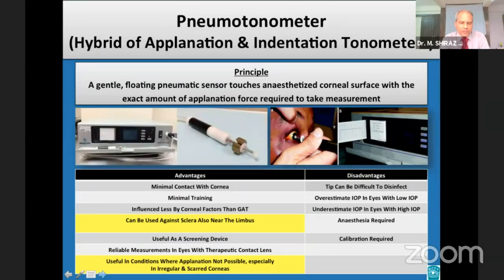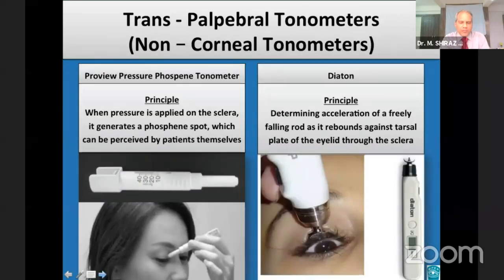Pneumotonometry provides reasonably accurate IOP readings across the range of corneal thicknesses and corneal pathology. Additionally, it can be used against the sclera near the limbus with IOP results nearly identical to those achieved by corneal contact. Recently, instruments have been developed that measure IOP through the eyelid over the sclera, obviating the need for topical anesthesia and the risk of eye-to-eye transfer of infection.